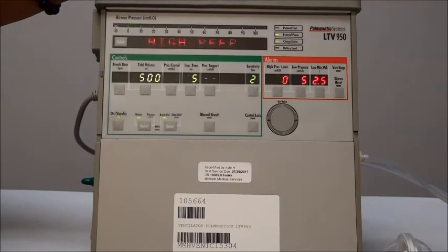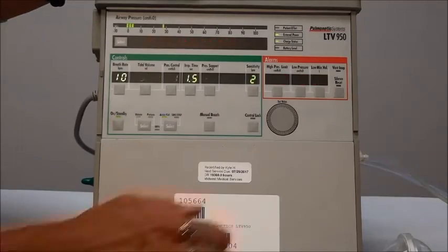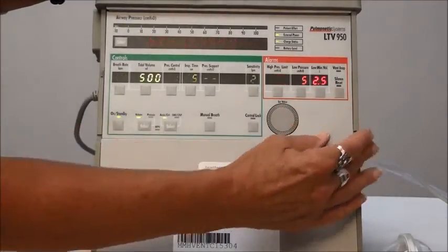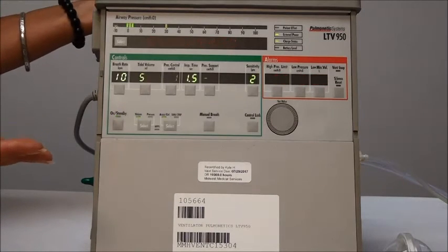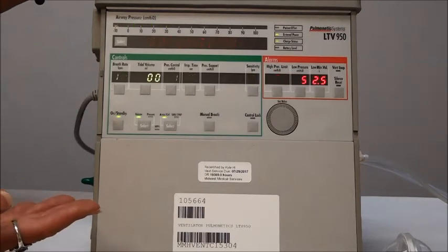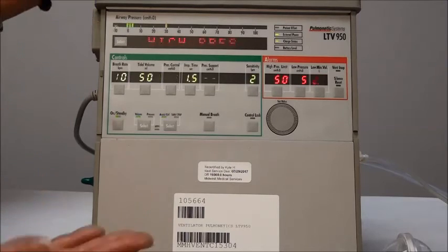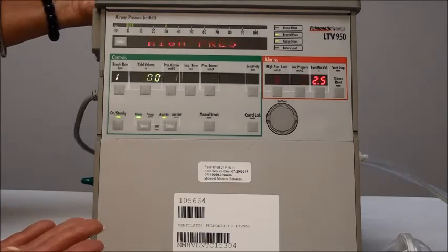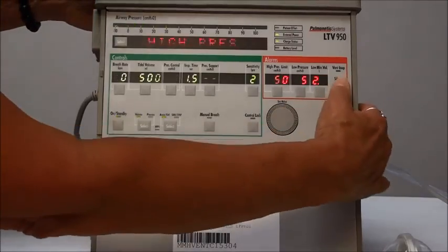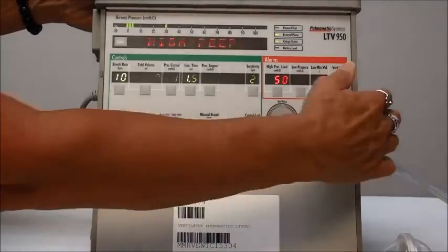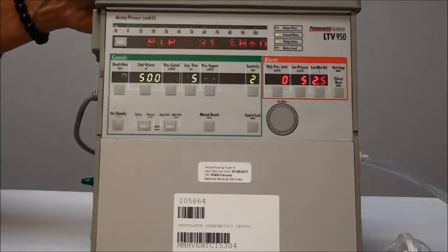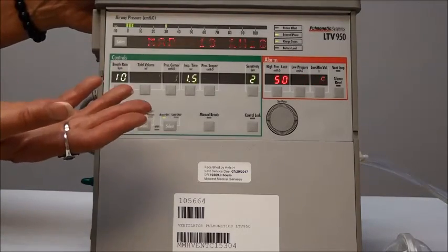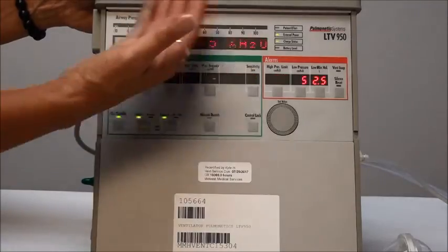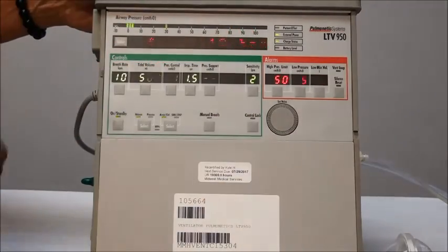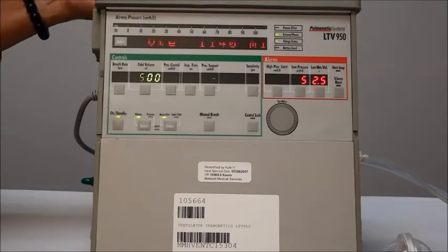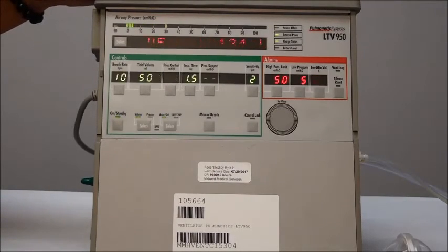So what I would do is I'd want to come and look at my patient, make sure they're okay, and then I'm going to try and determine what needs to be done. Maybe they coughed, and that was what caused that high pressure alarm. Maybe it's continuously high pressuring because your patient needs to be suctioned. You would need to solve the problem, and then you can come over and hit the reset button, and everything will go back to normal. Now, if you hit the reset button and you keep getting an alarm, or you keep getting an alarm flashing visually in the screen, you haven't solved your problem, and you need to continue to figure out what the problem is.